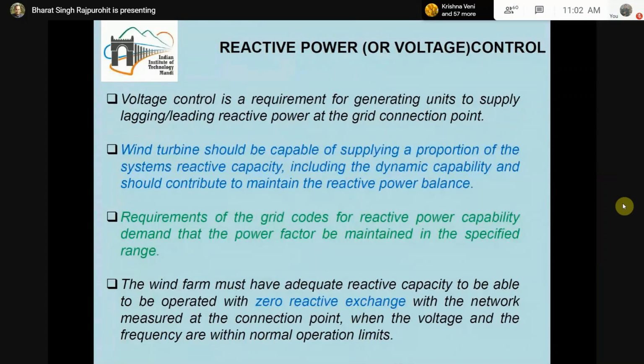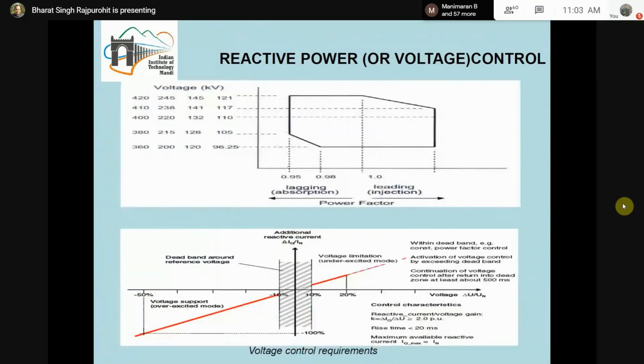By utilizing these power electronic converters, the overall wind energy conversion system will be able to inject reactive power as well as take reactive power, based on the ratings of the converters and the machine. So this is very much possible. So this can be addressed. Some such curves are shown here. The figure below is from a German grid code. This is a very strict requirement.